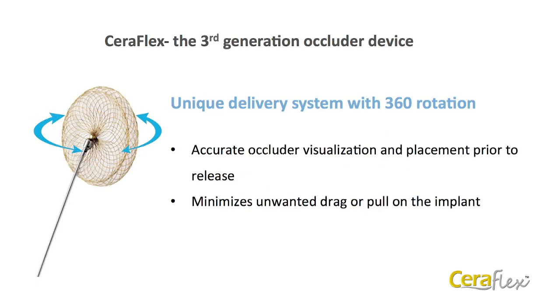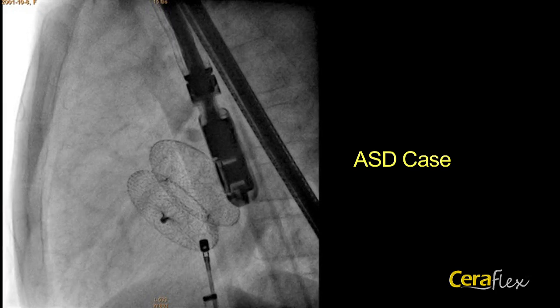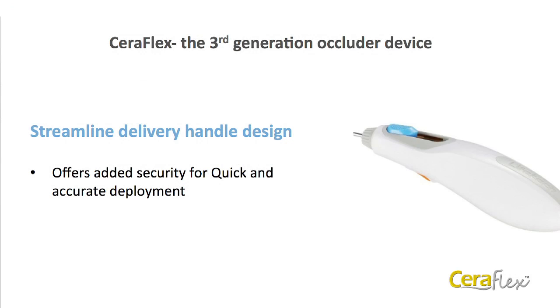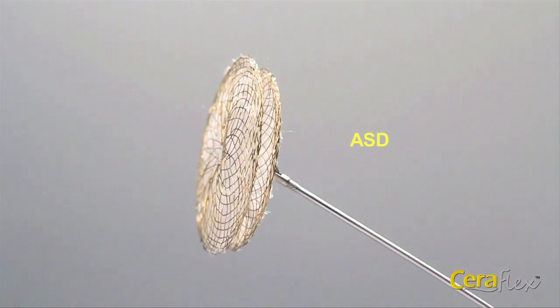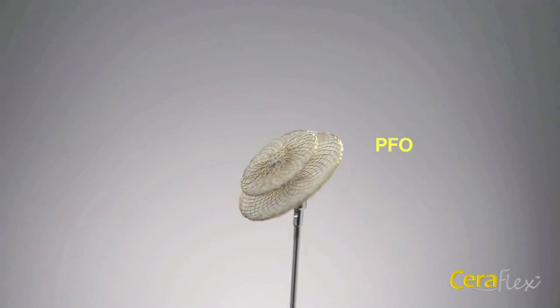The CeraFlex features a unique delivery system with 360-degree rotation. It allows for accurate occluder visualization and placement prior to release and minimizes unwanted drag or pull on the implant. Once deployed, the occluder may be observed in final position in the septal wall before release. The CeraFlex closure system also features a streamlined delivery handle design for quick and accurate deployment. The CeraFlex occluders are available for treatment of ASD, MF-ASD, PFO, and PDA.